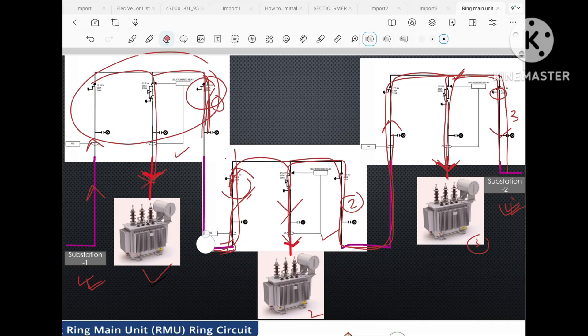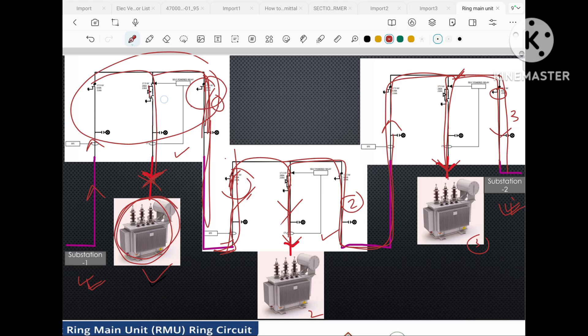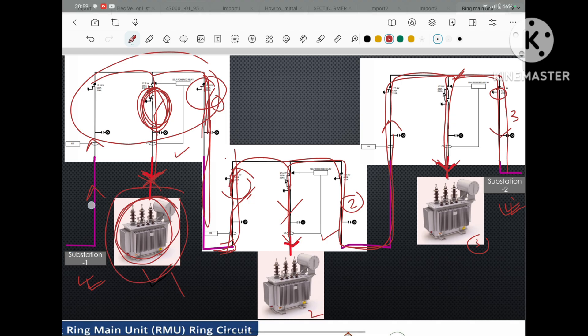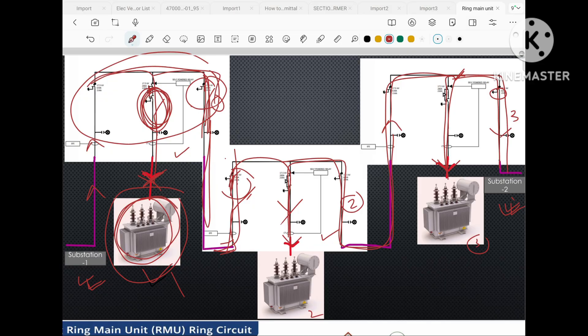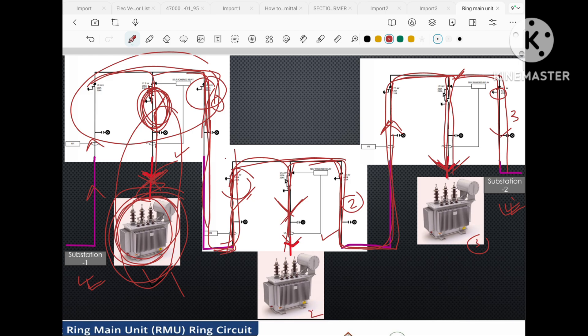Now let us take another example: this time the fault does not happen between ring main units one and two but somewhere at the transformer level side. What we will do is disconnect the circuit breaker and disconnector in order to disconnect this transformer from the system. Then the power flow will be from substation one to ring main unit one, ring main unit one will transfer power to ring main unit two, ring main unit two will provide power to transformer two and pass power to ring main unit three, which will supply transformer three. The faulty transformer system is now isolated from the energized system and we can do the maintenance. After maintenance, we reconnect the disconnector and turn on the circuit breaker to restore supply to that transformer.